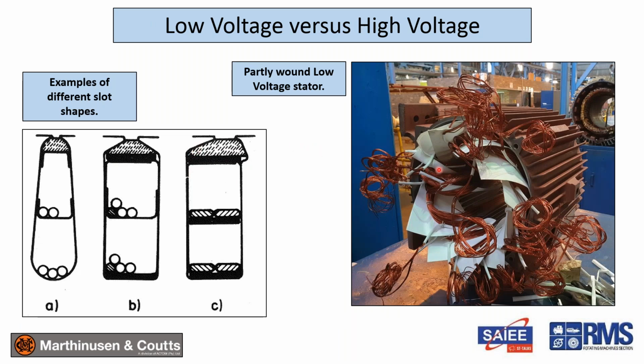Here's a low voltage machine, partly wound. Sometimes I think it's amazing that they actually completely wound these things when they look like this. Your different slot designs, most of them are this type on the left here. So you have your slot liner around the outside and your round wire and your wedge that fits in at the top. But again, the principles are the same. The machines are much smaller, the voltages are much lower. So with smaller machines, there's less relevance to differential thermal expansion and things like that.